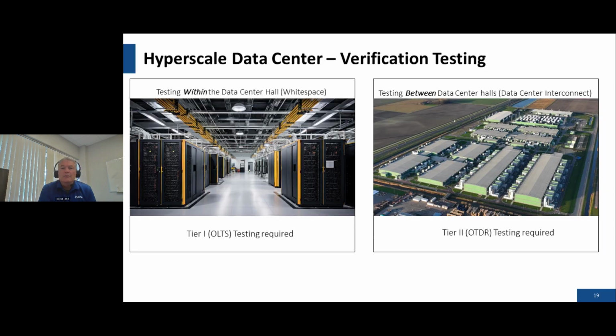Just to start, I should make the caveat that data center test plans really vary from operator to operator. But we've seen some common threads across most of them. One being that the fiber test equipment of choice within the data center, what they call the white space, is really the optical loss test sets, the OLTs. You may also hear the term tier one certifier, which refers to the piece of equipment that does the actual insertion loss testing.